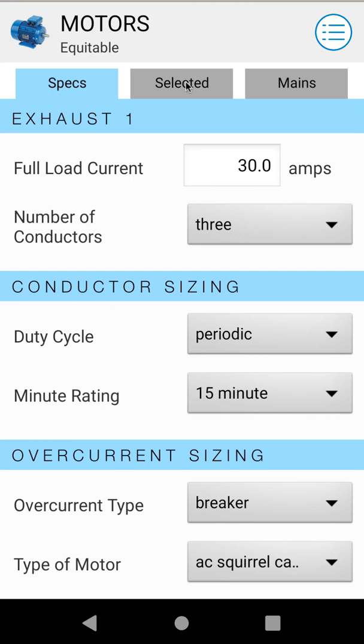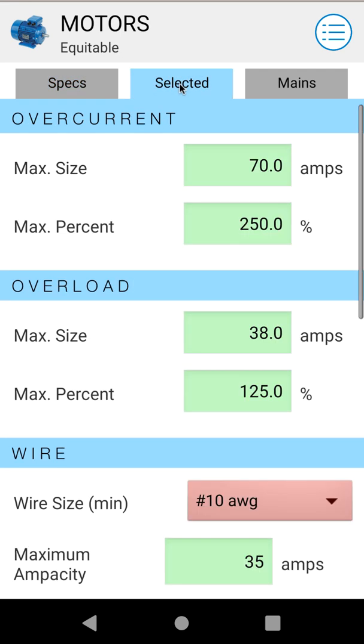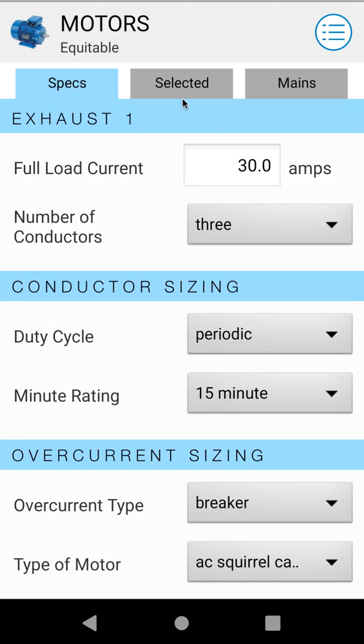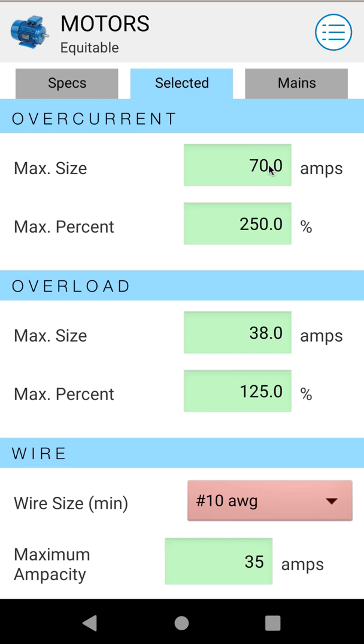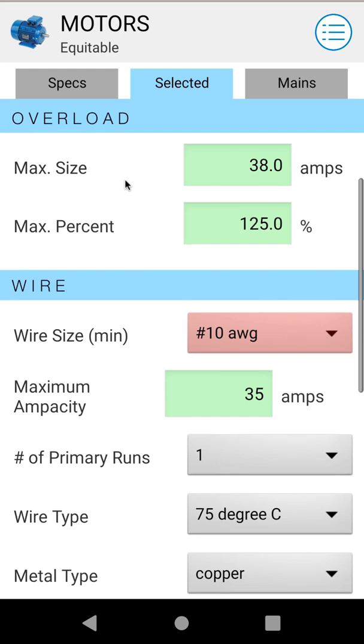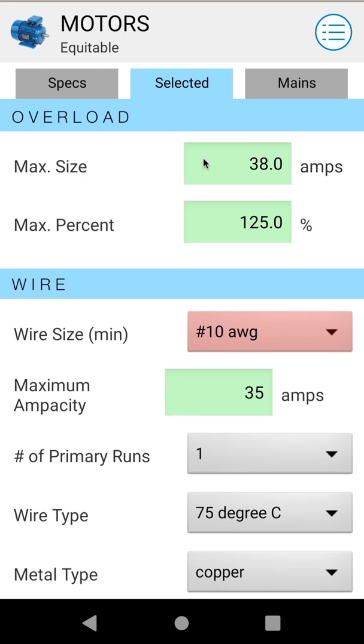Once you have all your numbers in, you can go to your results. In this case only one motor is selected so we'll go to our Selected motor. This gives our overcurrent sizing — our maximum overcurrent in amps and our maximum percentage, which is over FLA. We can go up to 250% over our FLA, which we specified as 30 amps, giving us 70 amps. Then we go down to our overload sizing — max size here is 125% of FLA, which is calculated to 38 amps.